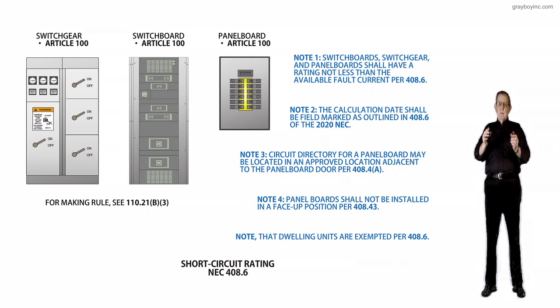But just remember, in most all jurisdictions, you have 10 kA circuit breakers in dwelling units and 5 kA in the old existing neighborhoods. So your short circuit is more regulated than it is in commercial and industrial type locations.